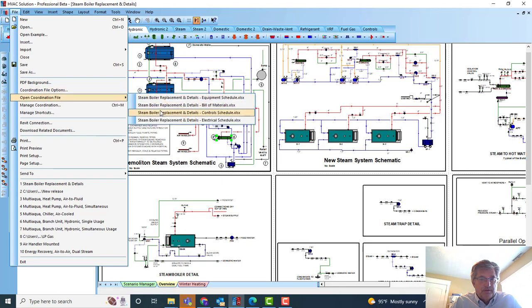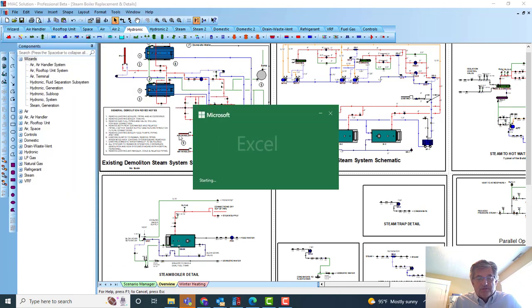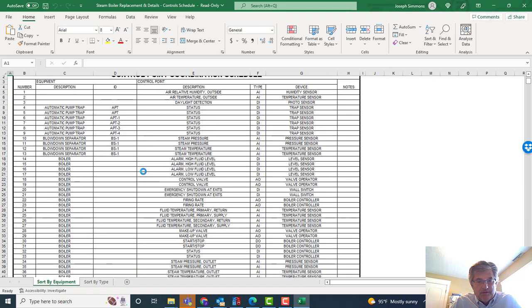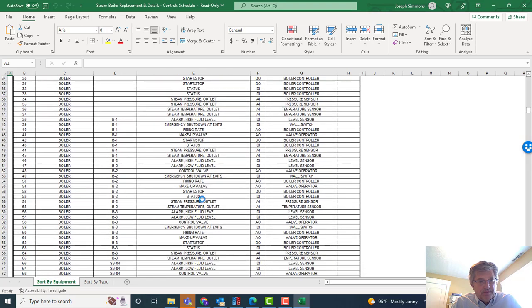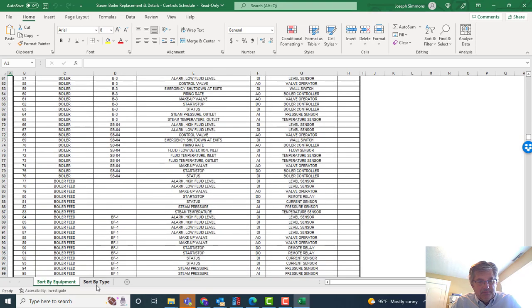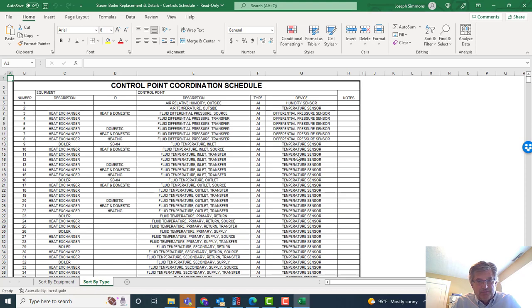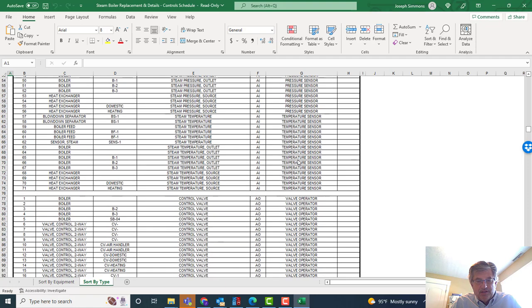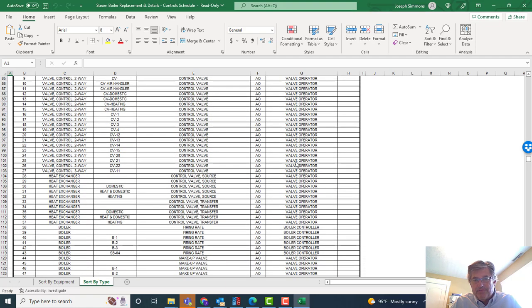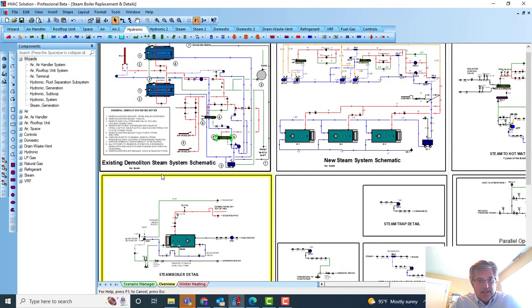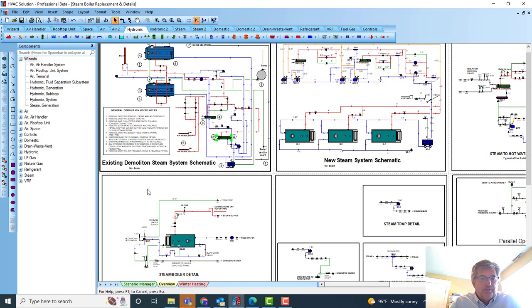Controls, integral, external, the different things that would be fluid sensors. And so by just going in there and me checking what I wanted, then I automatically had created for me a point schedule that they would be able to have for the contractor as well. Open there, the control schedule. This would be every point that's needed for the pumps—see mostly sensors on that. Boilers, alarms. And then if you want to sort it by type, there's all the differential pressure sensors for the heat exchangers, temperature sensors for heat exchangers, just down the list. Created very easily by just checking the boxes on and off on what I wanted. And then the last schedule in there was electrical. Anything that needed power, we created an electrical schedule so I can get that to the contractor so they know what kind of power is needed on the project.